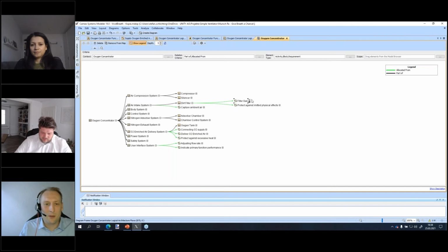And if I drill down more to the filter gas, in this case, we also actually see now here's an example to a certain set of requirements that are actually linked to it that we wanted to fulfill and that we said is relevant before we can really transmit it or put it into action inside of the hospitals. For example, that we need to filter biological contaminants, dust, and of course other stuff, and that is specified, of course, in more details in the requirement specification.